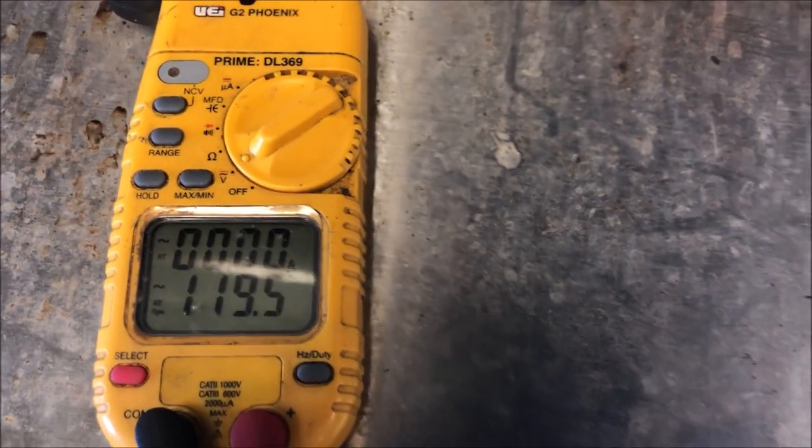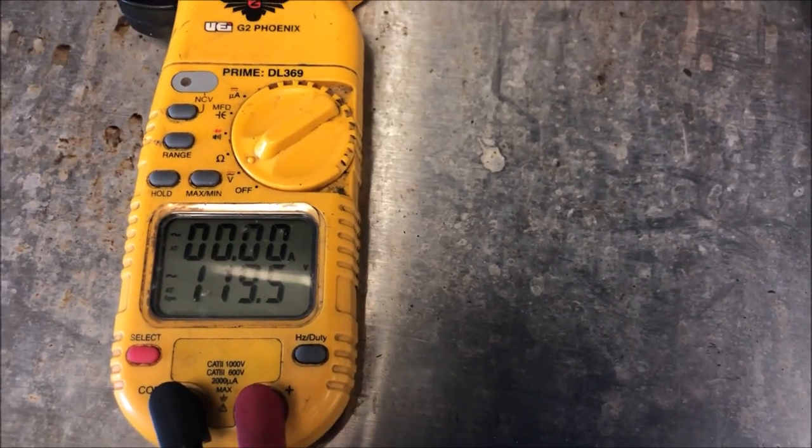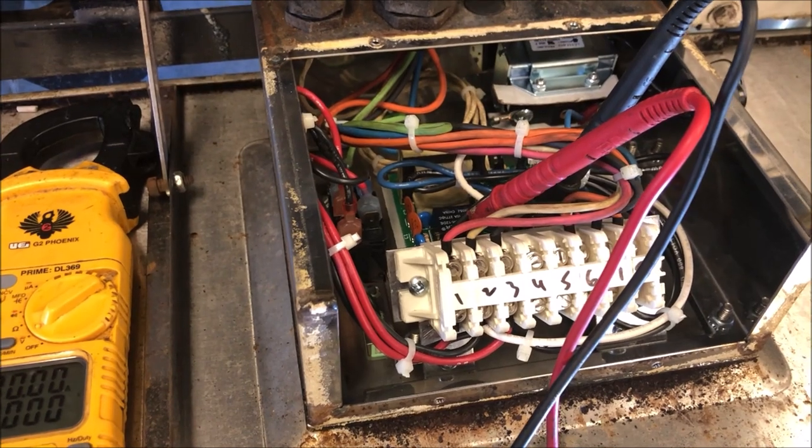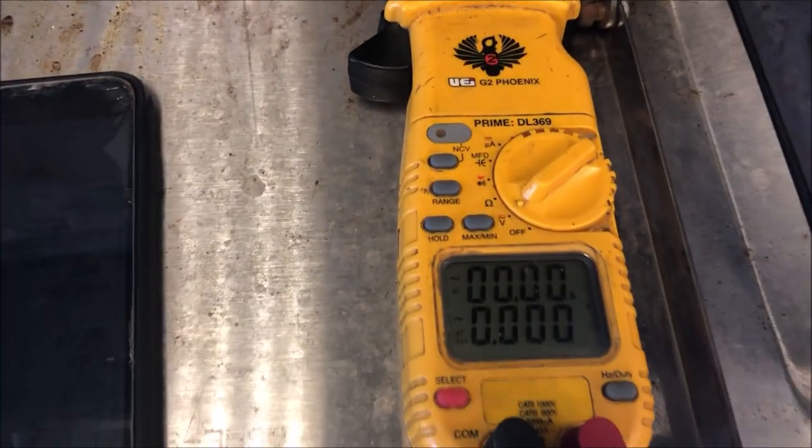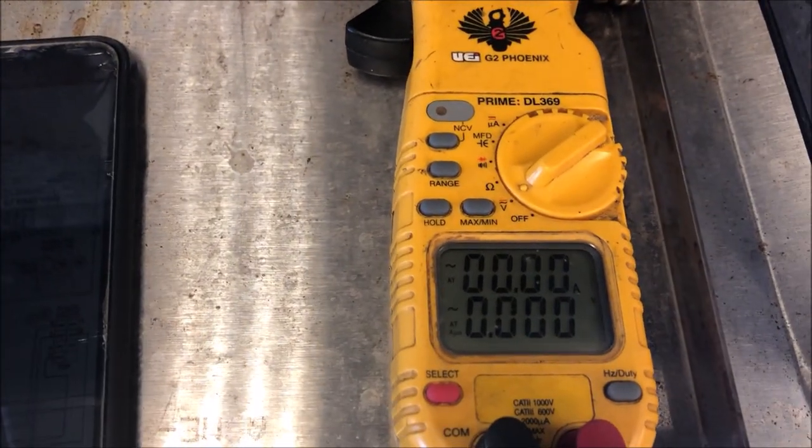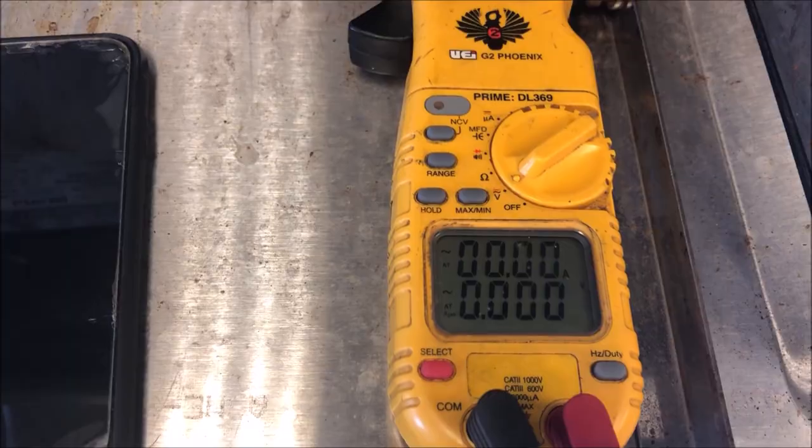Alright so let's start by testing pin 6 and 7 - we got 120 volts from the transformer to the board, that's good. Let's go test our pin 9 now and we're getting zero volts there which is interesting.